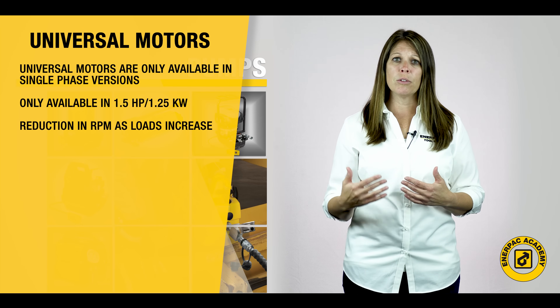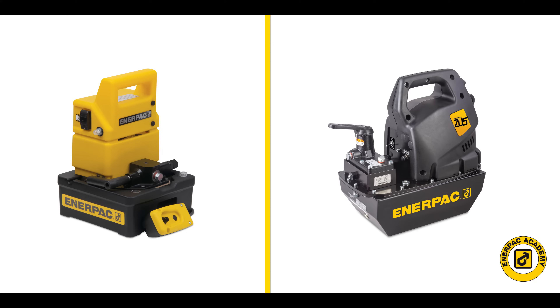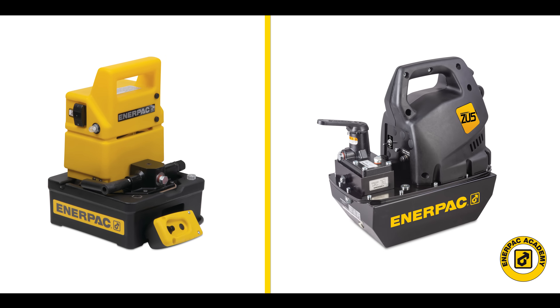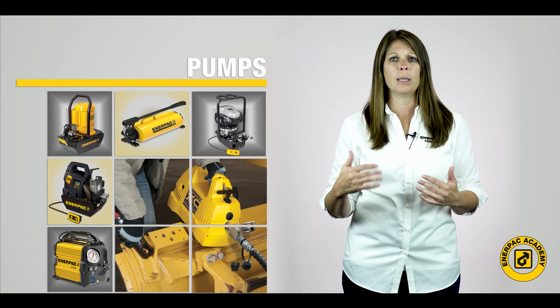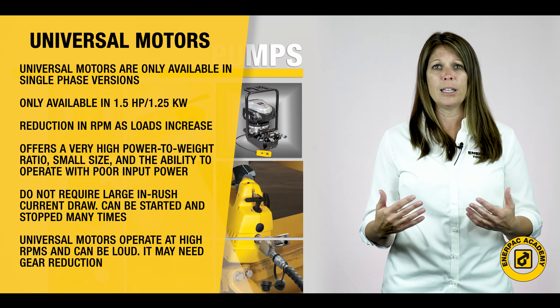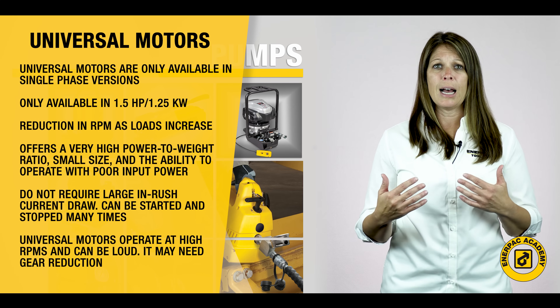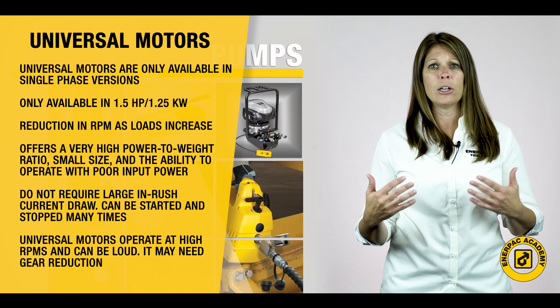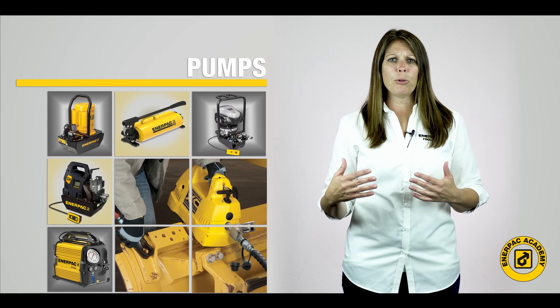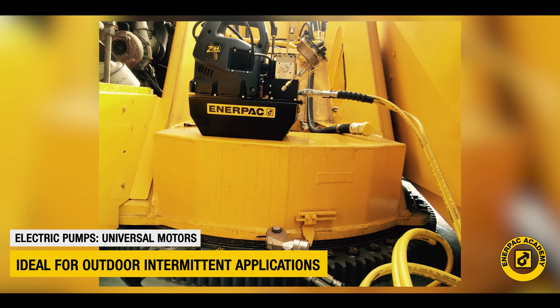The pump flow performance with each of these motors may vary slightly. The universal electric motor, found in the Enerpac PU and ZU series pumps, offers a very high power to weight ratio, small size, and the ability to operate with poor input power. These pumps do not require large in-rush current draw when starting and can be started and stopped many times. Universal motors operate at high RPM ranges, so they tend to have higher sound levels and may require a gear reduction for proper pump operation. These parameters make these motor-pump combinations ideal for intermittent duty applications, usually outdoors, with ease of transport and operation on generators or poor power supplies.